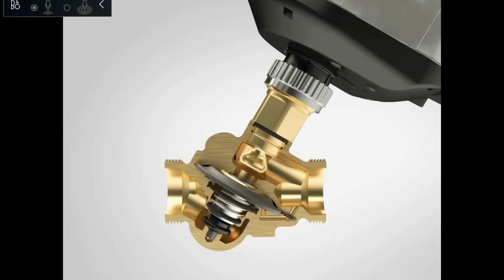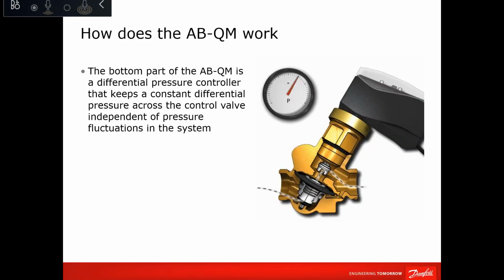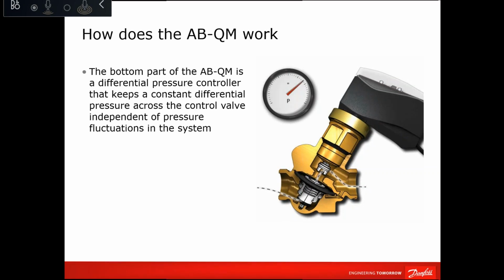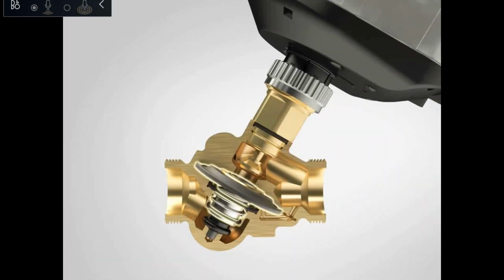So this is the upper part, which is the modulating part, moving up and down, only responding to the command coming from the thermostat or the BMS to control the temperature. The lower part, or the bottom part, is the differential pressure control that keeps constant differential pressure independent of the system pressure fluctuation. And here you can see the movement.